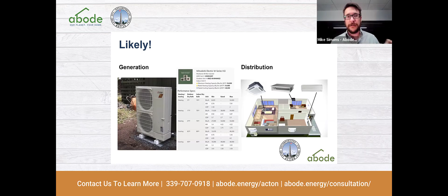The tricky thing when thinking about this technology is related to the sizing of the outdoor units and the number of indoor units you can have on it. That's kind of the biggest issue, as I've had a few hundred consultations about this, but it's somewhat easy to deal with because you can always switch one of those ductless units to a ducted unit. So for that Cape we had earlier, you could put a ducted unit inside the 2nd floor and duct it to both bedrooms, and then just have 2 ductless units on the 1st floor, and now having just 3 units can make sense.